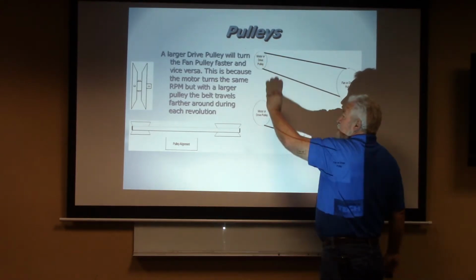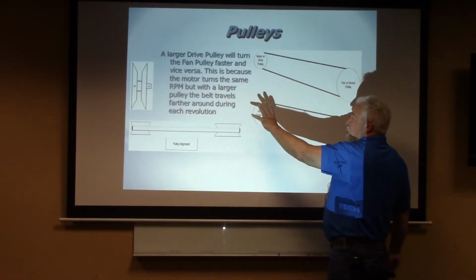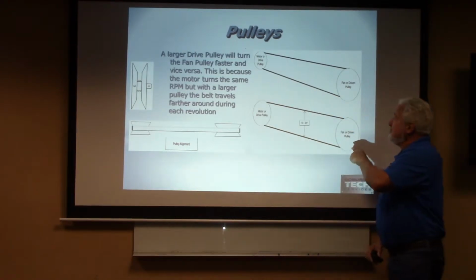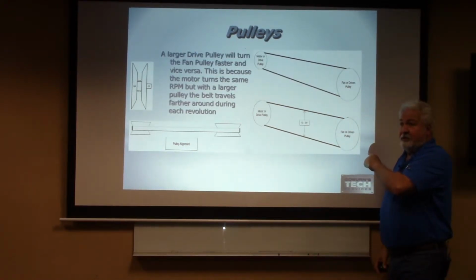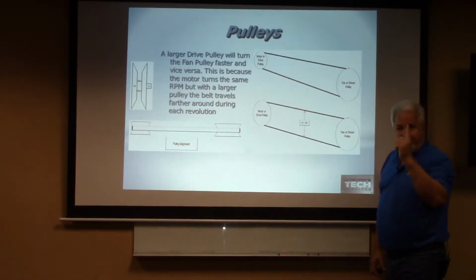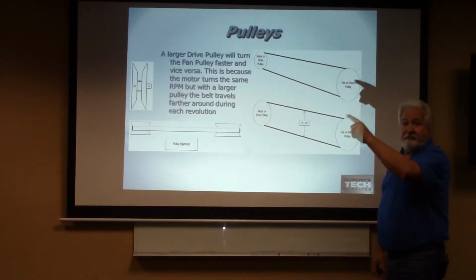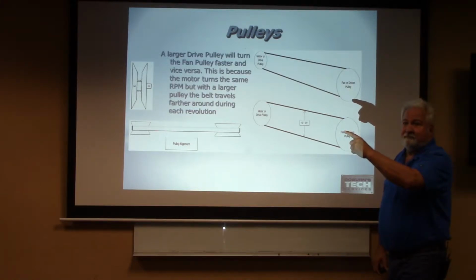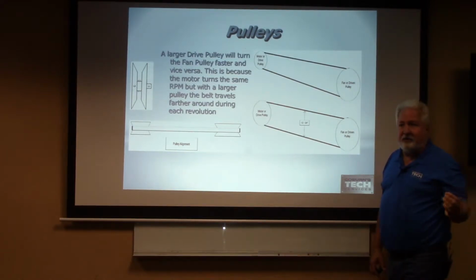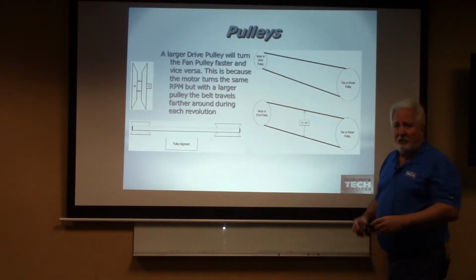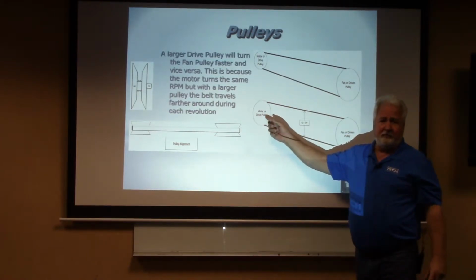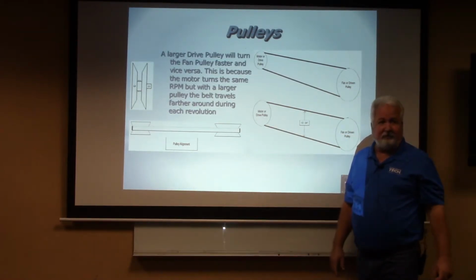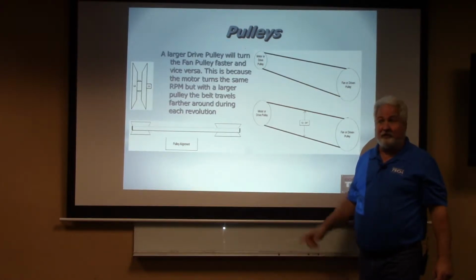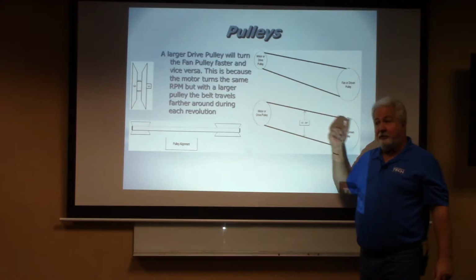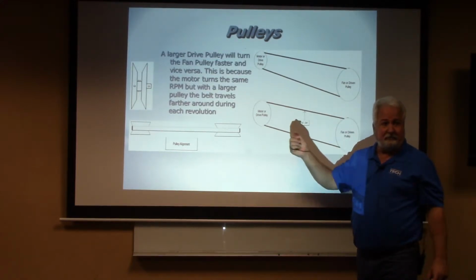By changing the drive pulley from a small drive pulley to a larger drive pulley, 1 rotation is going to change the output of that fan. Is that right? Is it going to change the CFM? Yes. Is it going to change the RPM of that motor? RPM is going to be the same. Is everybody getting that? That's the kind of question they may ask on a NATE exam where you're going to have to stop and think that one through. What happens when I change that drive pulley? Does it change the CFM? Yes. Does it change the RPM? RPM of what? RPM of the drive pulley, the RPM of the motor? No, it doesn't.